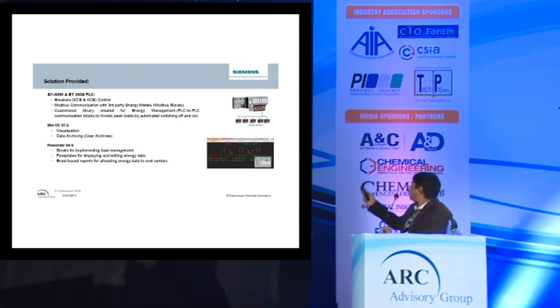The local control system has all the energy meters - each building may have 100 to 150 energy meters, connected floor-wise, even load-wise, for all the outgoings. These energy meters give data to the PLC - it's like data acquisition. And this local PLC can control, meaning do load shedding and load balancing on your load, whatever is actually required.